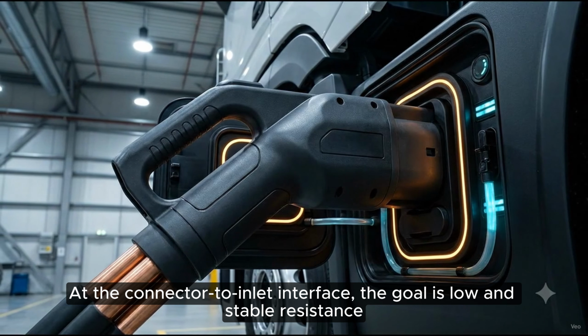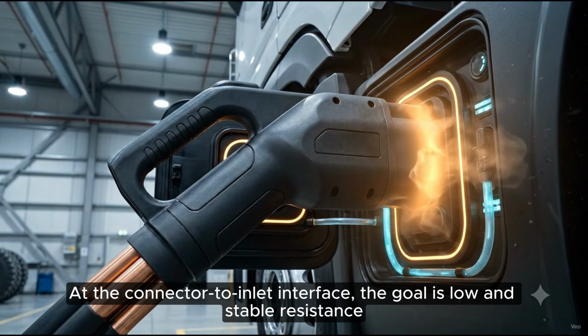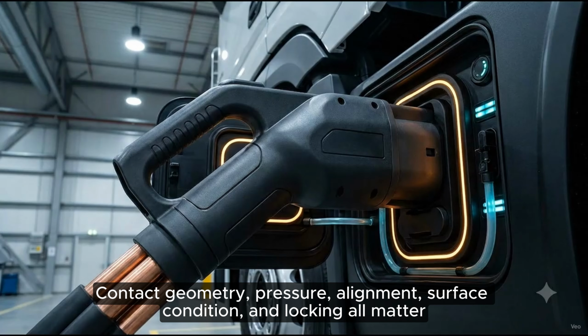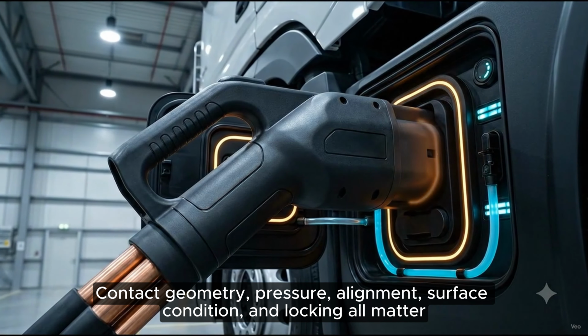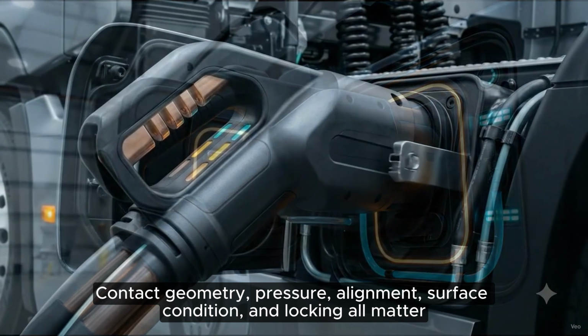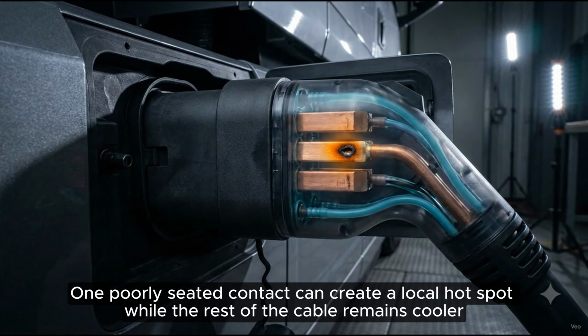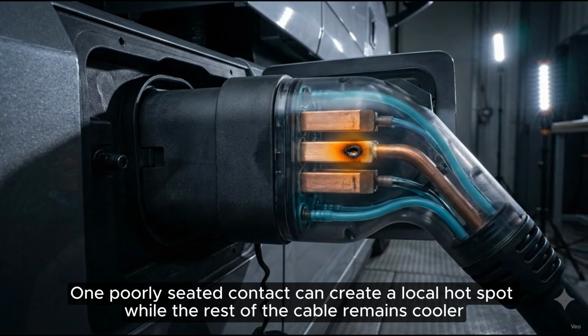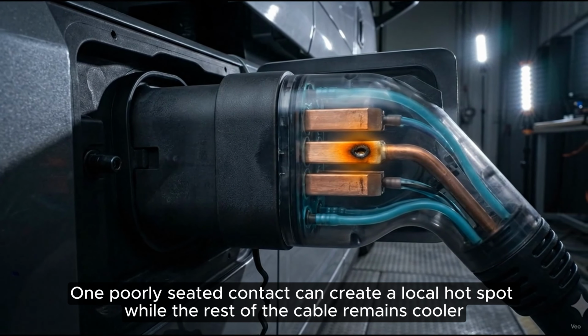At the connector-to-inlet interface, the goal is low and stable resistance. Contact geometry, pressure, alignment, surface condition, and locking all matter. One poorly seated contact can create a local hotspot, while the rest of the cable remains cooler.